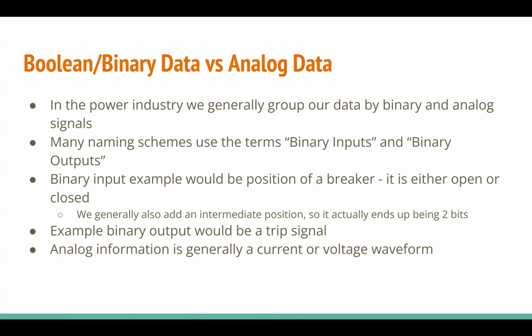In the power industry, we generally use the terms binary inputs and binary outputs. A binary input is something where we're reading the current status of a breaker—is it open or closed. A binary output is us telling something to do something, or telling something else the status of something—so if we wanted to control the breaker to open or close, we would use a binary output.